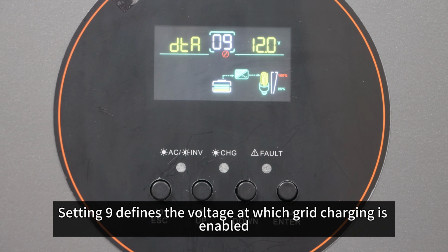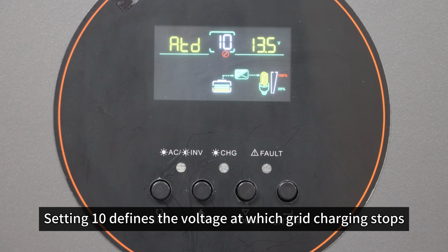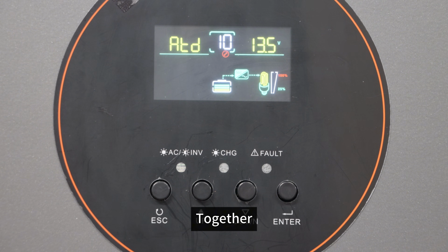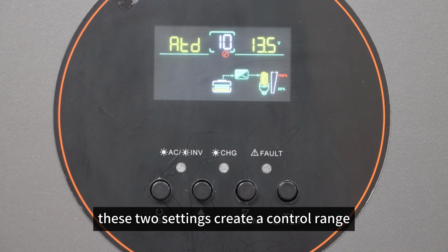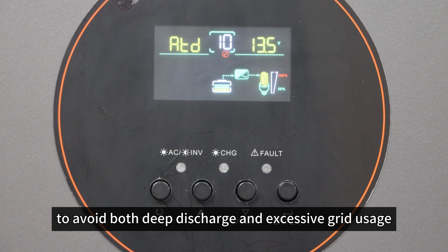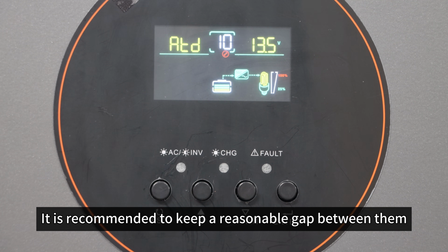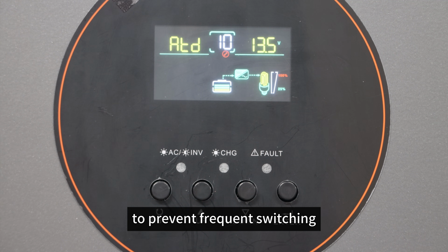Setting 9 defines the voltage at which grid charging is enabled. Setting 10 defines the voltage at which grid charging stops. Together, these two settings create a control range to avoid both deep discharge and excessive grid usage. It is recommended to keep a reasonable gap between them to prevent frequent switching.